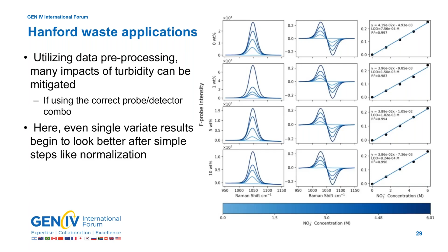And the last slide shows the signal strength as a function of nitrate concentration. The x-axis here is nitrate concentration. From 0 all the way up to 10 weight percent, we have essentially the same sensitivity. Again, that's because we do the pre-processing step of the first derivative, and we also do some normalization using the water hydroxide band to normalize our spectra. I just want to point out the slope of these lines is about 4 times 10 to the minus second for each one of these applications, from 0 to 10 weight percent solids, meaning the sensitivity of this measurement has not been degraded by increasing to high weight percent solids. So the combination of probe design and pre-processing steps really does a very good job.